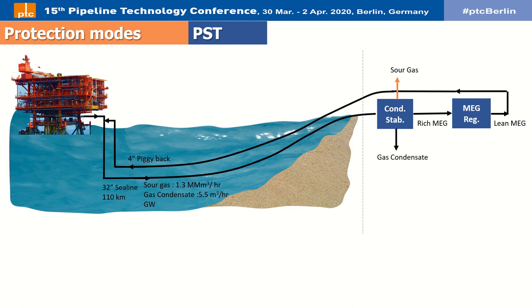MEG is injected at platform departure to prevent both hydrate formation and corrosion in the sea lines. The onshore MEG regeneration unit provides a solution of 70% MEG containing 1.5 volume percent methyl diethanolamine as a pH control additive to prevent corrosion issues within the sea lines. The in-situ pH at the arriving point shall be kept above 7.04 to ensure effective corrosion mitigation.